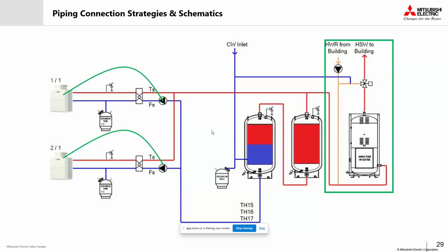And then next we have a swing tank or temperature maintenance tank, which is also an item that's commonly included to manage recirculation from the building. And then we have temperature probes throughout the system, and those are going to ensure precise on-off control for optimizing efficiency, comfort, and system longevity for our heat pumps.